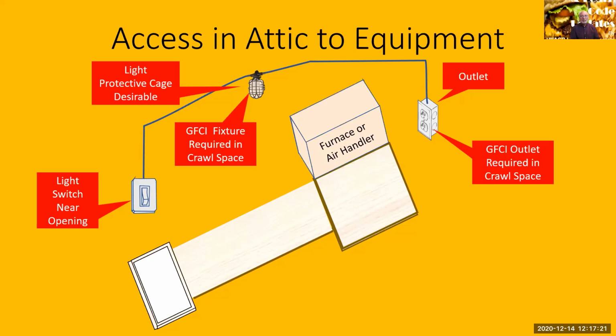Okay, so in the crawl space now, when a person goes in and they're going to change out a furnace or air handler, and that house was built in the 80s, this may be the first time anything has changed. Does that mean that the HVAC person is going to be responsible for putting in that GFCI fixture and the GFCI outlet? Well, we haven't really got into that, but now on the change out, you are upgrading your equipment under the floor or you're adding new equipment. So at that point, it has changed.